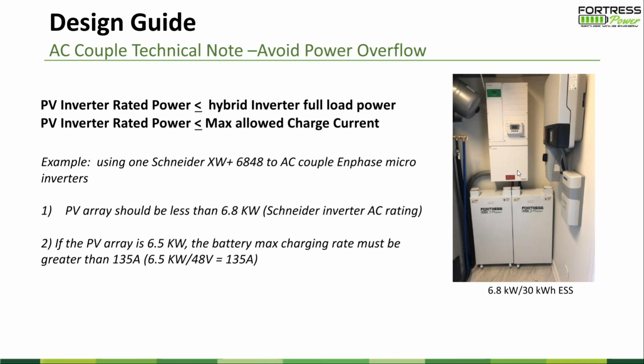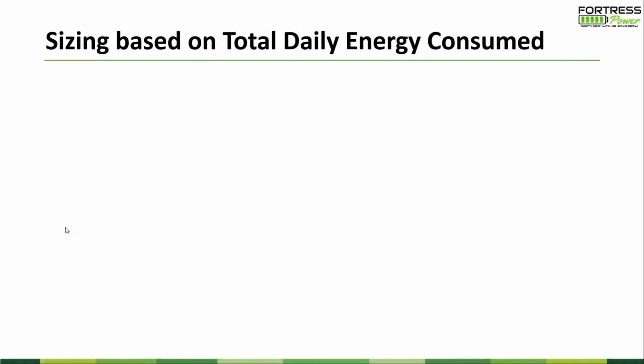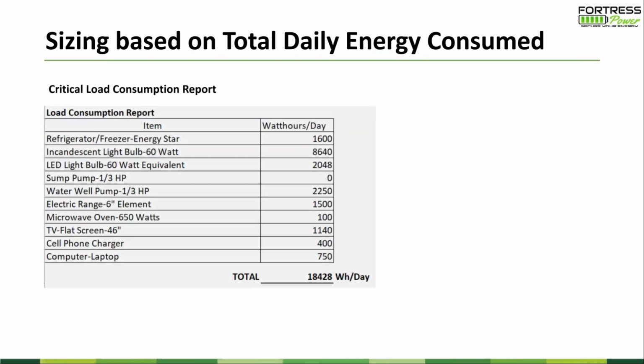The technical notes I gave to everybody are so that people are aware of this. I know in the market, the PV inverter and the storage inverter have a certain mechanism to regulate the PV production. We call it frequency shifting. It triggers a frequency shift from the storage inverter to try to stop the PV inverter's production if too much power comes to the storage inverter. That's very good technology, but Jeremy, you need to go back to the last slide.